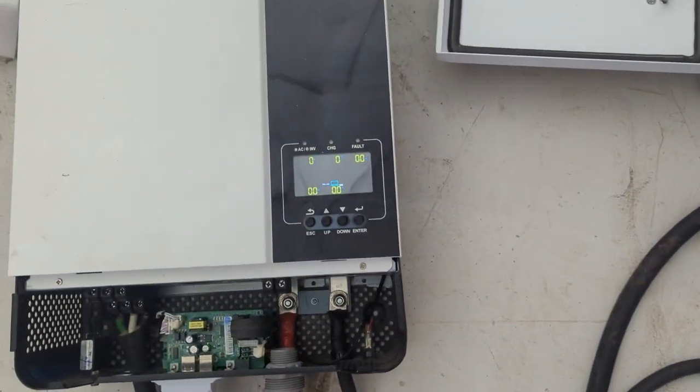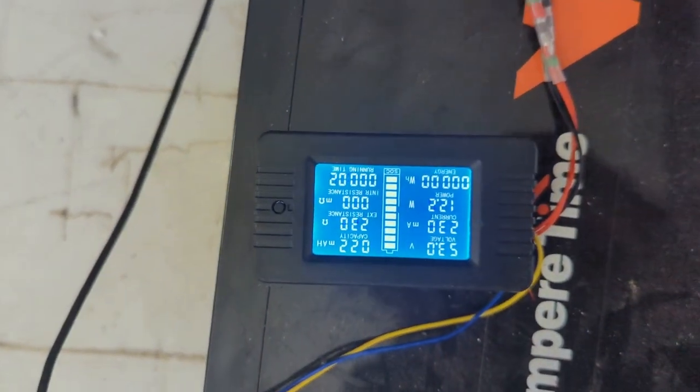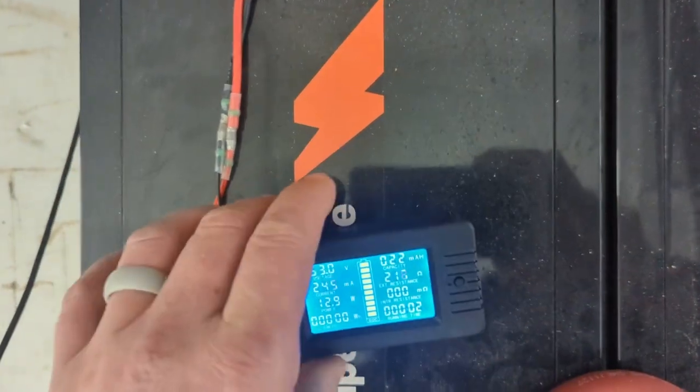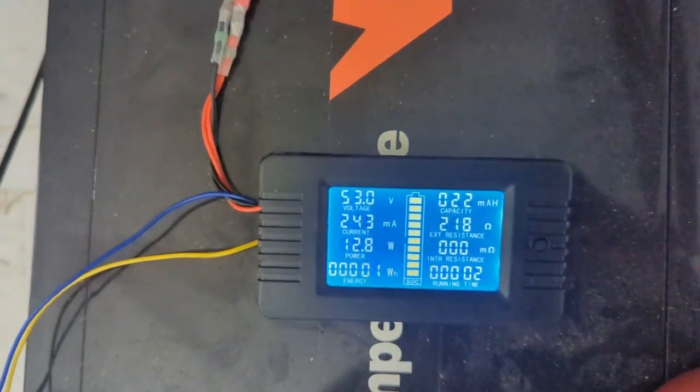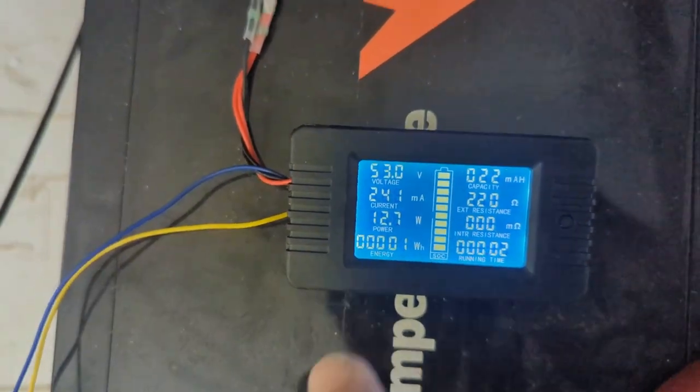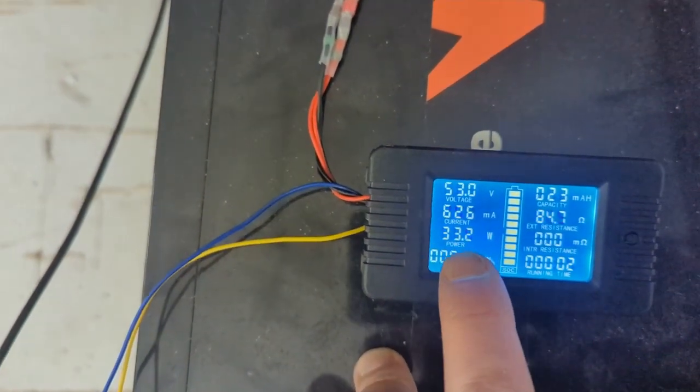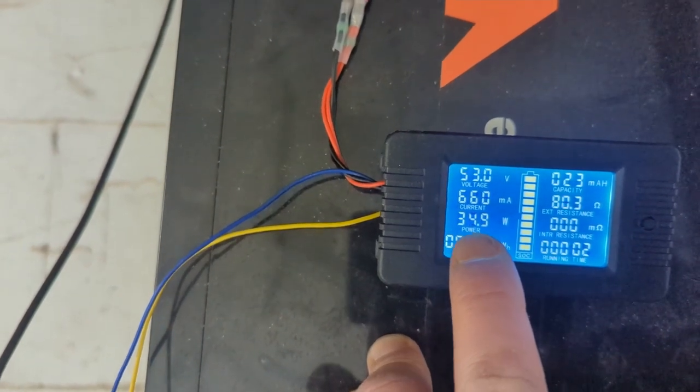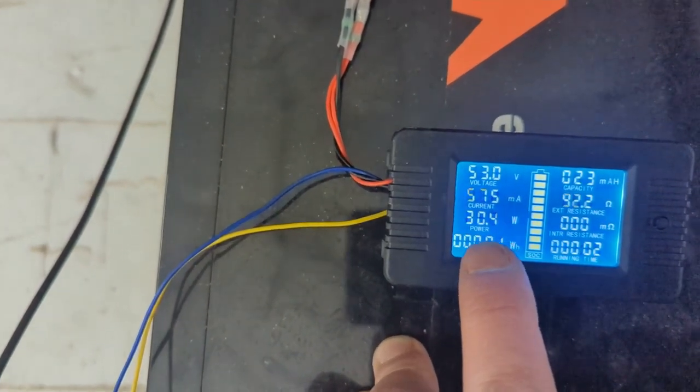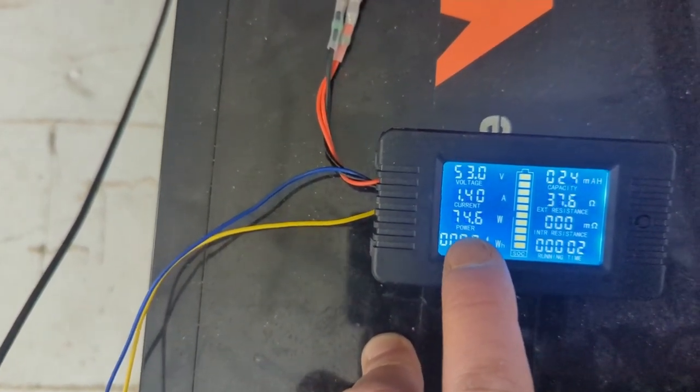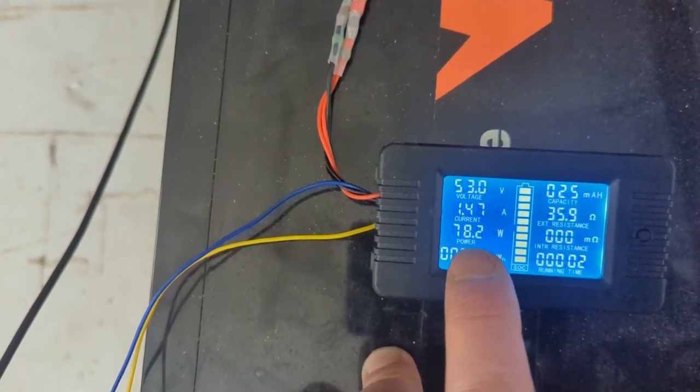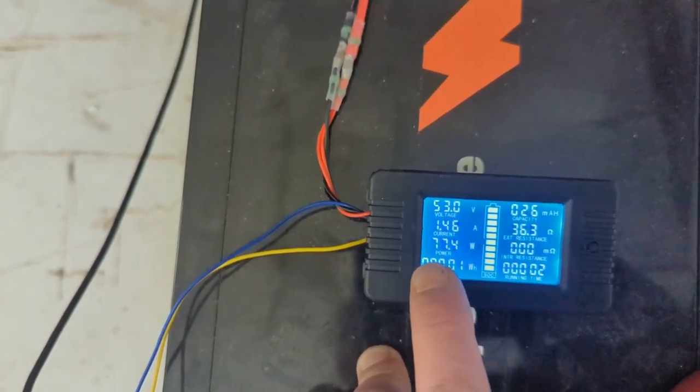Now we see that coming up and now we have a consumption. Oh boy that's been upside down the whole time. Come on, now we have a consumption of about 33 watts here. And I think people have tested these things and they're right around 50 to 60 watts of self-consumption. I mean I'm reading 77 watts of self-consumption here.